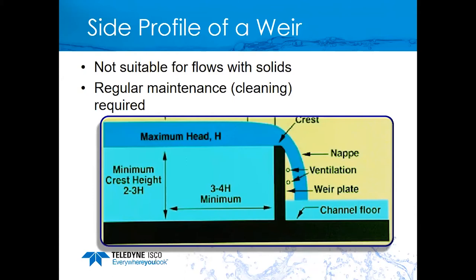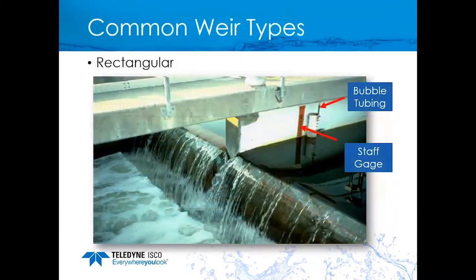Here is an example of a rectangular weir using bubbler technology to read the level — an ultrasonic sensor could also be used. If a staff gauge is present, it makes on-site calibration easier. Without a staff gauge, one approach is to stop the flow and set the level to zero when the water equals the top of the crest.